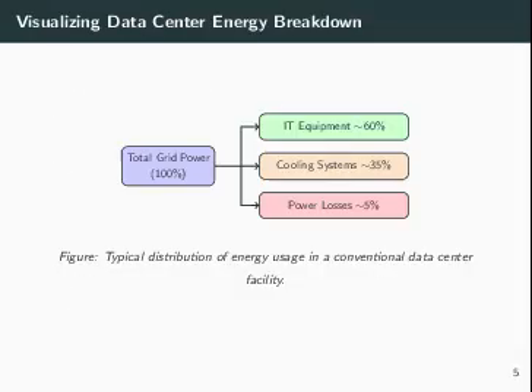This breakdown illustrates where power goes in a conventional data center facility. Roughly 60% of total grid power directly powers the IT equipment, such as compute servers and storage. Cooling systems account for about 35%, while power conversion and distribution losses make up the remaining 5%.